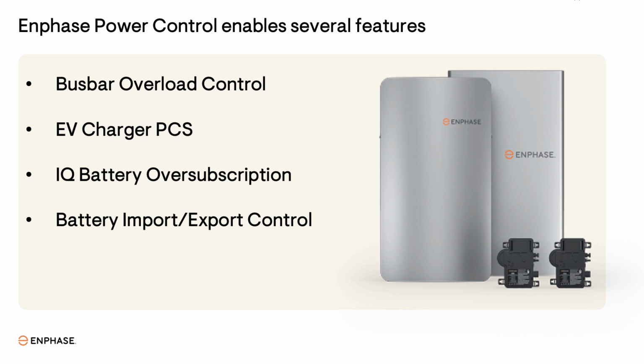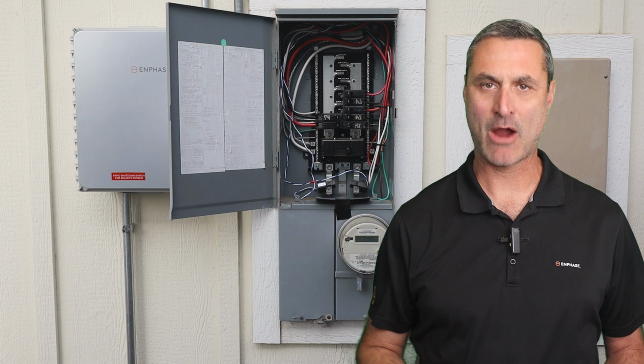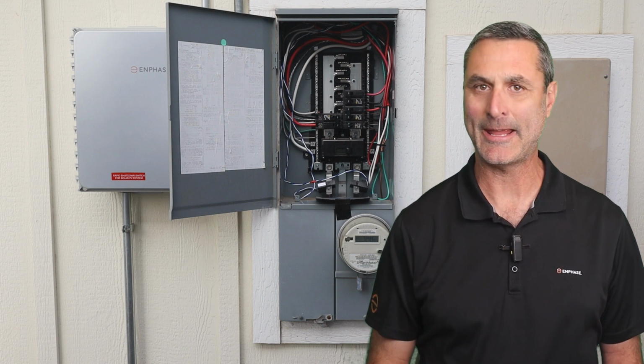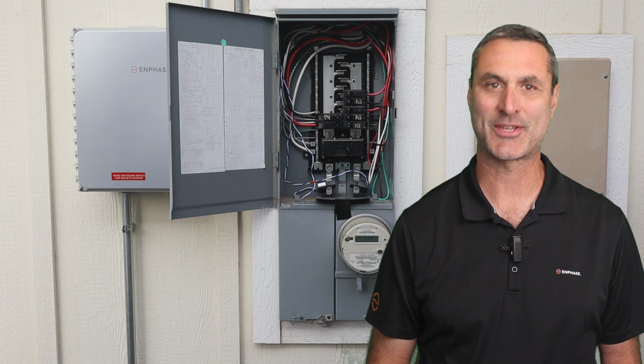Battery Import and Export Control. This feature gives homeowners control over the energy flow to and from the grid. Users can select import-only mode to prevent battery discharge to the grid, meeting specific utility requirements. Alternatively, export-only mode enables battery discharge to the grid, maximizing economic benefits under NEM 3.0 in California. Aggregate Power Export Limit. This feature allows installers to set limits on the total power exported to the grid, meeting specific utility requirements, and potentially avoiding transformer upgrade costs. While almost all of the existing power control features are for residential split-phase systems today, Enphase is enhancing these to cover commercial systems in the near future.